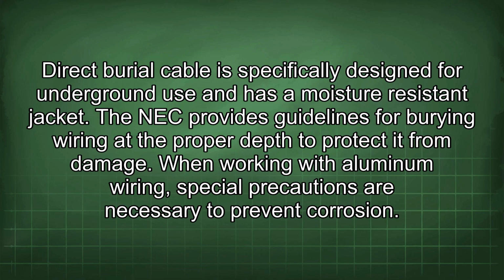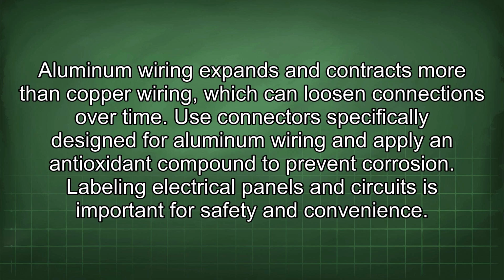When working with aluminum wiring, special precautions are necessary to prevent corrosion. Aluminum wiring expands and contracts more than copper wiring, which can loosen connections over time. Use connectors specifically designed for aluminum wiring and apply an antioxidant compound to prevent corrosion.